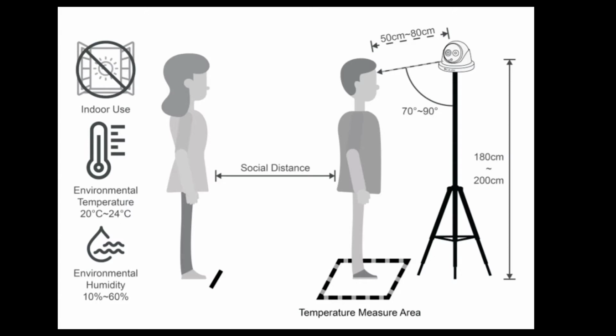So let's quickly go over a couple of important setup parameters. First, this camera is intended only for indoor use. It is not meant to be used outdoors or in direct sunlight. Second, we want to make sure that when we're reading temperatures that we're within a controlled temperature environment where the temperature is between 68 and 75 degrees Fahrenheit or 20 to 24 Celsius. And we want to make sure that the environmental humidity in our environment is between 10 to 60%.